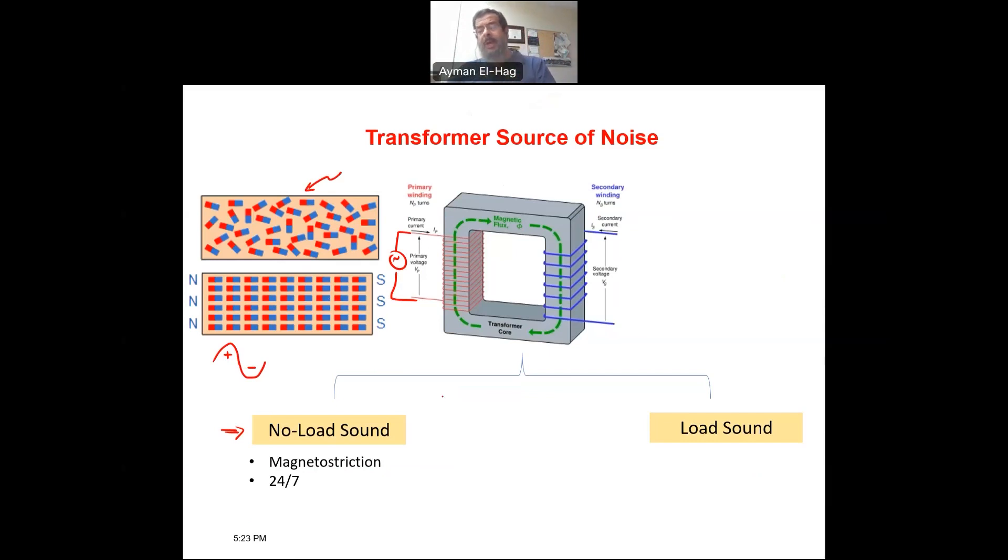But there is also another source of noise coming from the load current this time. And as we explained before, when the transformer is subjected to a short circuit there will be some very strong mechanical force that could be very destructive to the extent it damages the winding mechanically. Now here we are not talking about a fault. We are talking about a high level of current. So this will lead to strong magnetic force which will cause again vibration to the structure of the winding of the transformer.